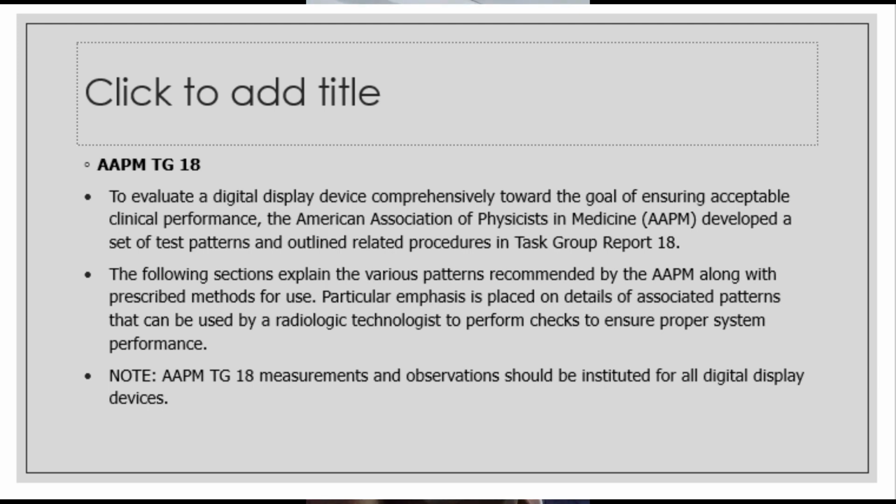AAPM TG-18. So, it is used to evaluate a digital display device comprehensively toward the goal of ensuring acceptable clinical performance, or your also known as the American Association of Physicists in Medicine. Okay, it developed a set of test patterns and outlined related procedures in Task Group Report 18.